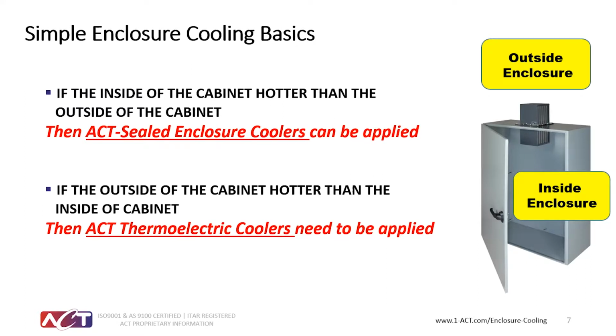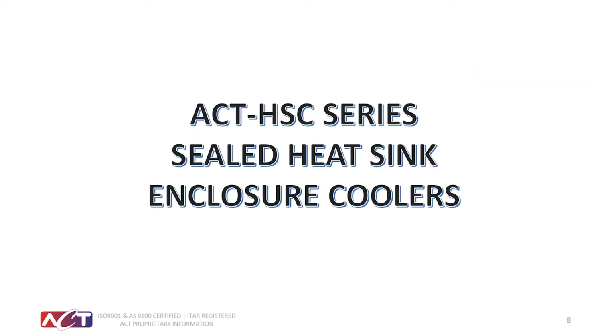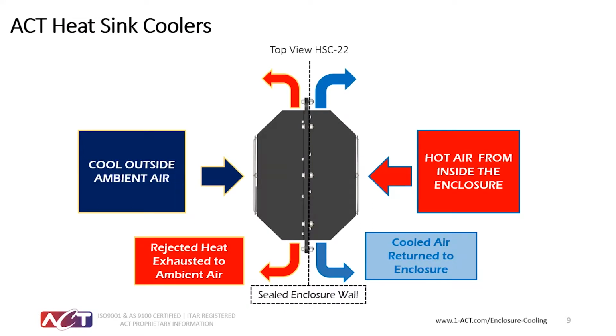ACT heat exchangers are a viable option, even with as little as a 5 to 10 degree temperature delta between the inside and outside of the enclosure. However, the larger the temperature gradient, the better the overall cooling capacity. The ACT HSC heatsink cooler is an air-to-air heat exchanger that efficiently removes heat from a sealed enclosure by simply transferring heat from a bonded heatsink on the inside of the cabinet through a sealed wall to a common bonded heatsink outside of the cabinet.